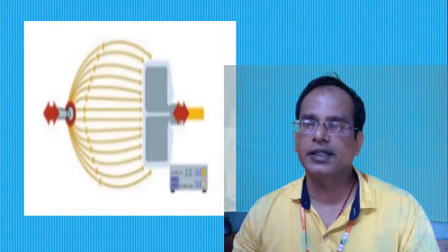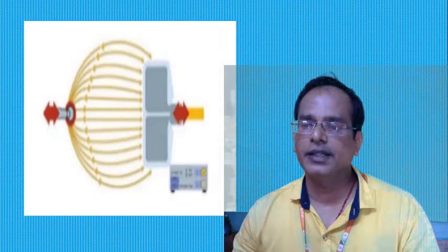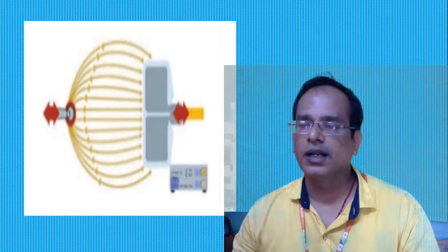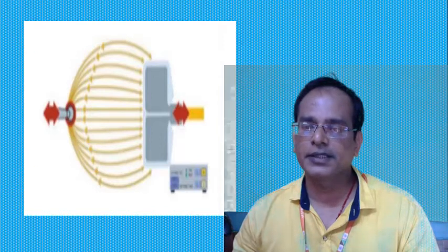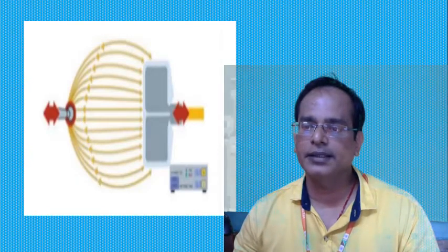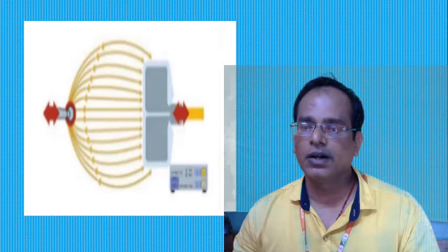The surface area and impedance can be compromised by excessive hair, adipose tissue, bony prominence, fluid invasion, adhesive failure, scar tissue, and many other variables. As a special consideration, patients with an implanted pacemaker and automated defibrillator, cochlear implant, implanted bone growth stimulator, body jewelry, or orthopedic implant should not go for this treatment.